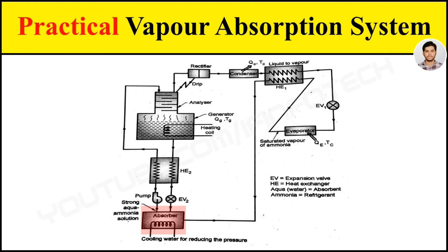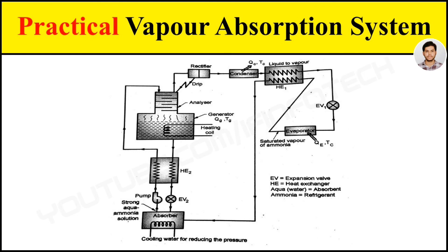This strong aqua ammonia solution is pumped to the generator through the heat exchanger. The function of this heat exchanger is to provide cooling of the weak solution and heating of the strong solution. This operation saves the amount of cooling needed for the absorber and the amount of heat needed for the generator.